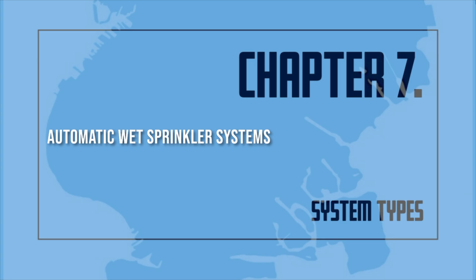The most commonly installed system is wet pipe systems, which have water in the piping at all times. This type of system is used where the temperature is maintained at a minimum of 40 degrees to prevent the system from freezing. Where temperatures drop below freezing, the ordinary wet pipe system cannot be used. There are two methods for using automatic sprinklers in places exposed to freezing temperatures. One method is a system where water enters the sprinkler piping only after a control valve is opened. These are dry pipe systems, deluge systems, or pre-action systems. The other method adds an antifreeze solution to the water in the wet pipe system. The antifreeze solution is a mixture of chemicals designed to prevent the water from freezing.